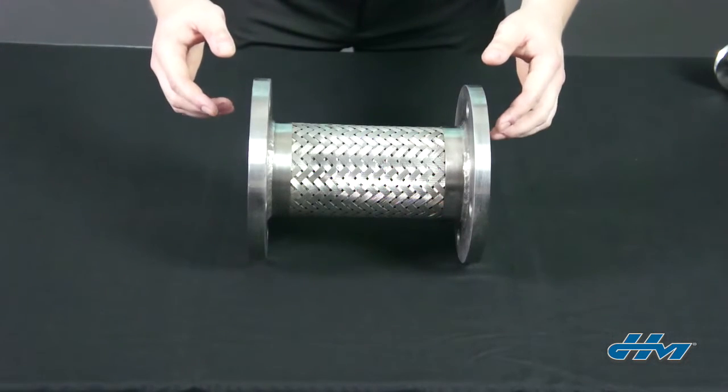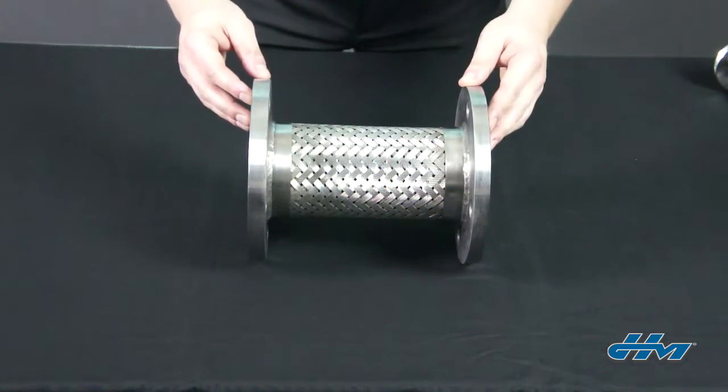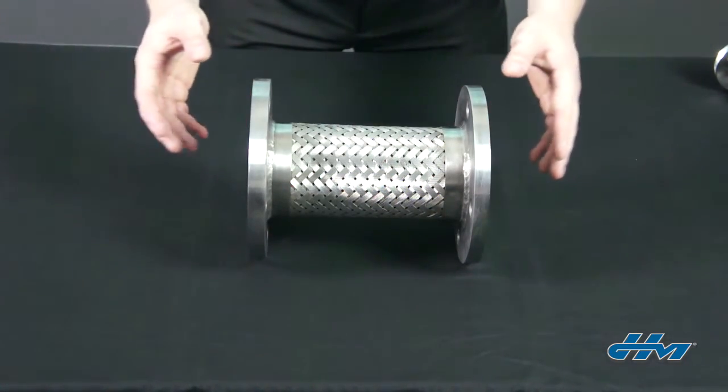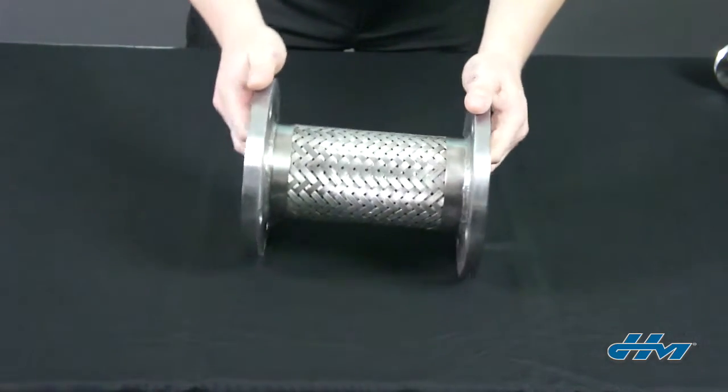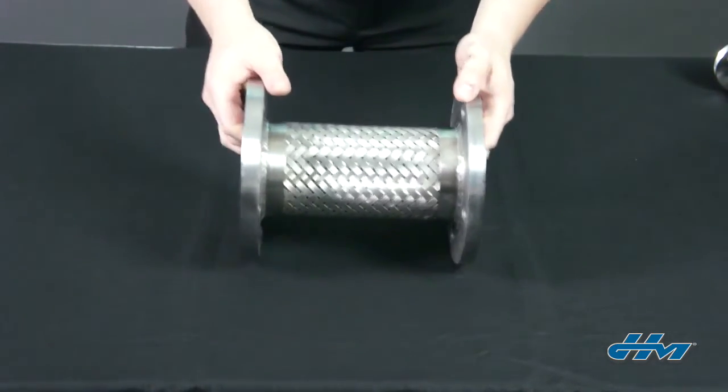Torquing the hose during installation is common and can be an issue. If the existing piping does not have any kind of swivel or rotation, don't use an assembly with fixed end fittings at both ends. Otherwise, installation could torque the assembly and strain it in service.